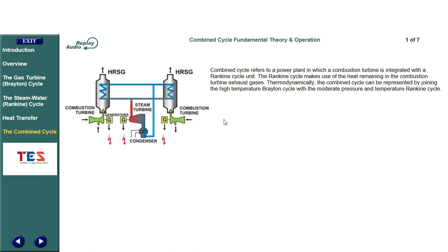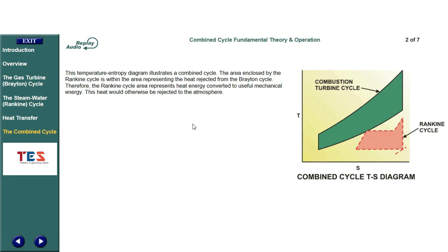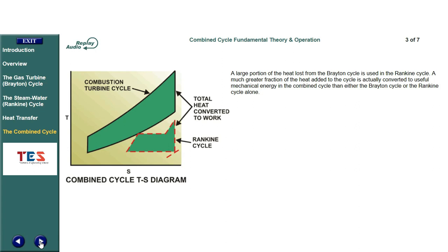Combined cycle refers to a power plant in which a combustion turbine is integrated with a Rankine cycle unit, which makes use of the heat remaining in the combustion turbine exhaust gases. Thermodynamically, the combined cycle can be represented by joining the high temperature Brayton cycle with the moderate pressure and temperature Rankine cycle. The area enclosed by the Rankine cycle on the temperature-entropy diagram is within the area representing the heat rejected from the Brayton cycle. Therefore, the Rankine cycle area represents heat energy converted to useful mechanical energy — heat that would otherwise be rejected. A much greater fraction of the heat added to the cycle is converted to useful mechanical energy in the combined cycle than in either the Brayton cycle or the Rankine cycle alone.